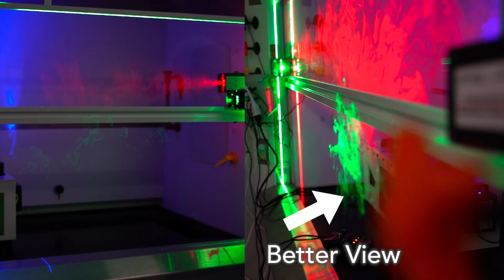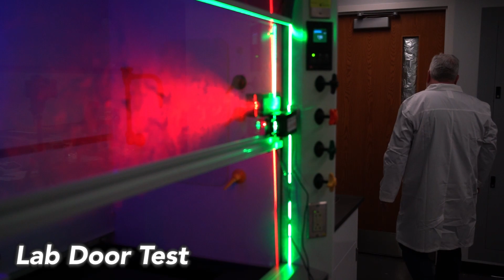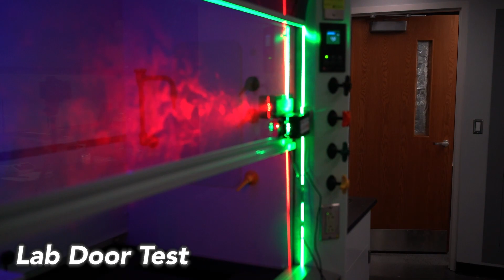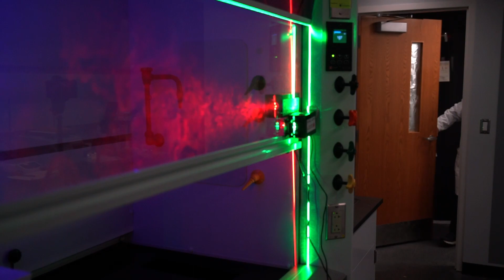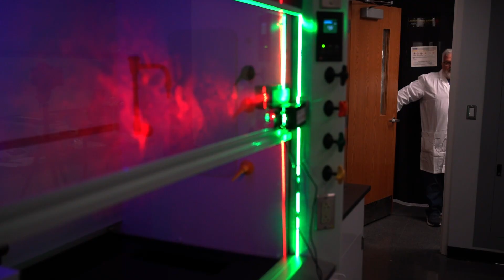Here's an example of failure from a poorly performing hood, and you can really tell that it sucked some of those fumes right past the green light and lit it up. Definite loss of containment there with the walk-by challenge. Containment is greatly impacted by the air balance of the room. Opening and closing the door causes the room balance to change. For the lab door challenge, just go open and close the lab door. See if the red smoke behind the sash changes in any way.